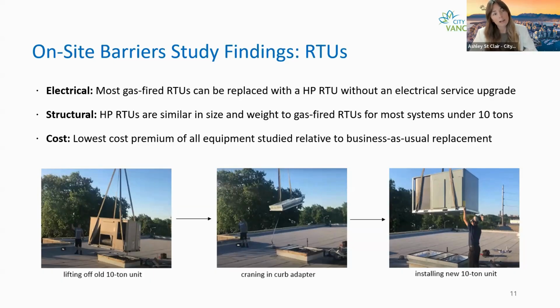And on the structural side of things, we found that heat pump RTUs are very much similar in size to gas-fired units. Especially when we're talking about units under 10 tons, the heat pump units were slightly heavier, but not in a meaningful way, where structurally you would need any significant reinforcement that would add a significant cost. When you get into the larger packaged units, the 15, 20 and 30 ton units, the weight differential we saw could grow. But for the vast majority of the smaller systems, there was minimal structural impact.